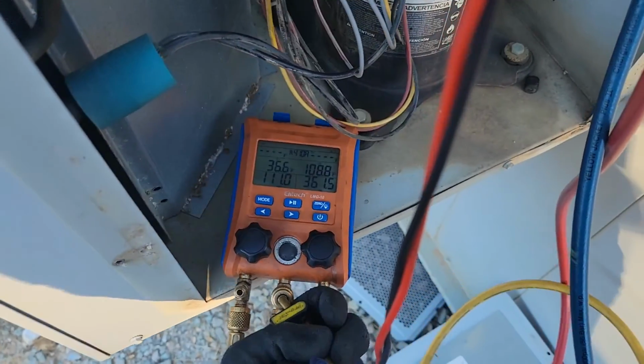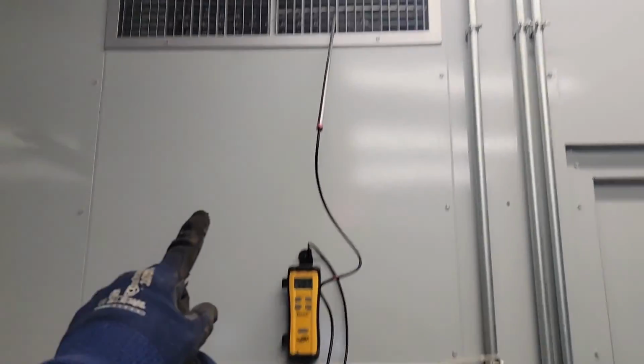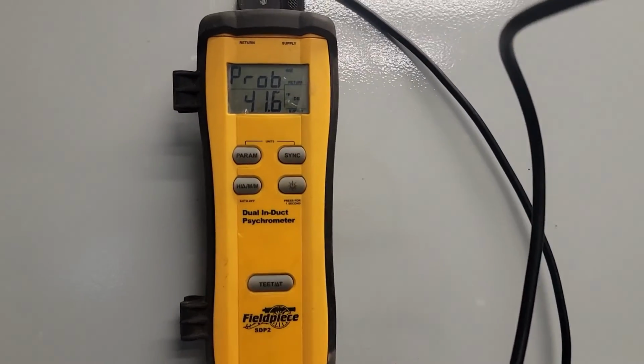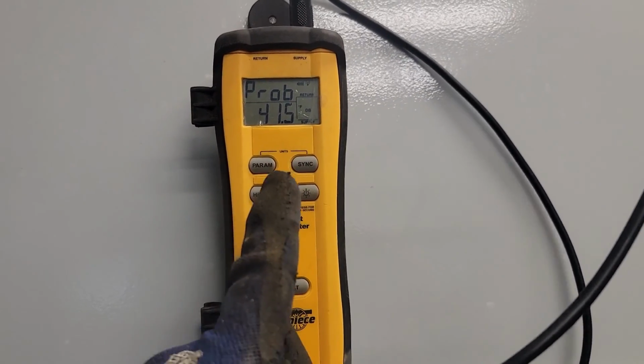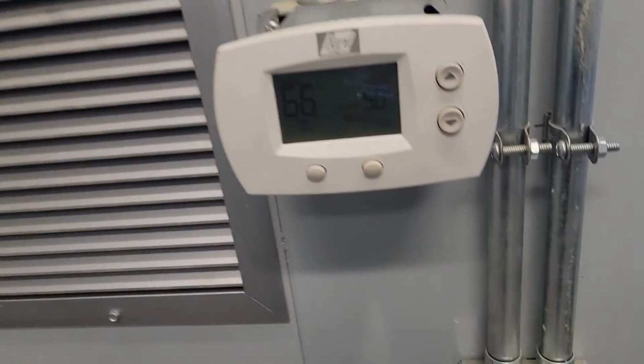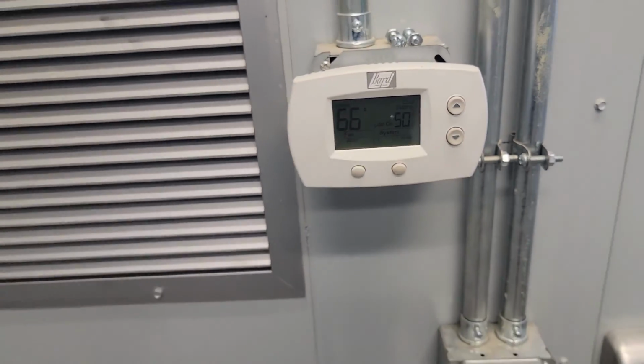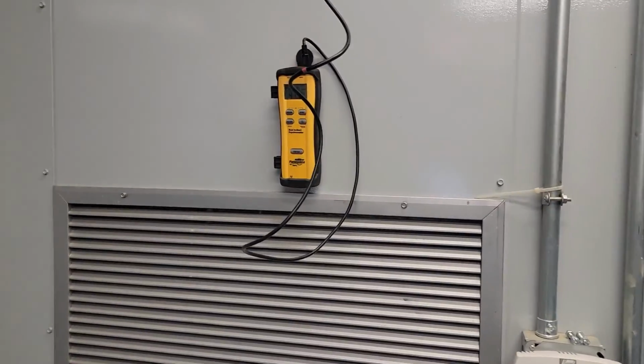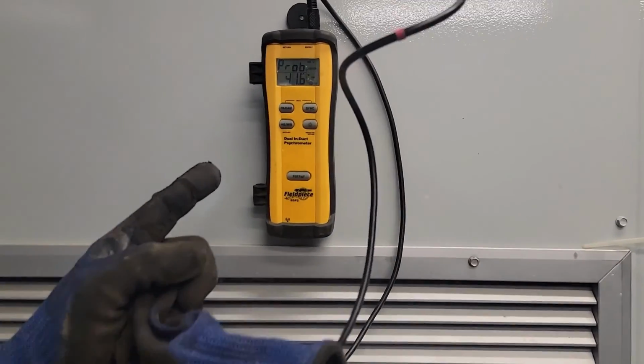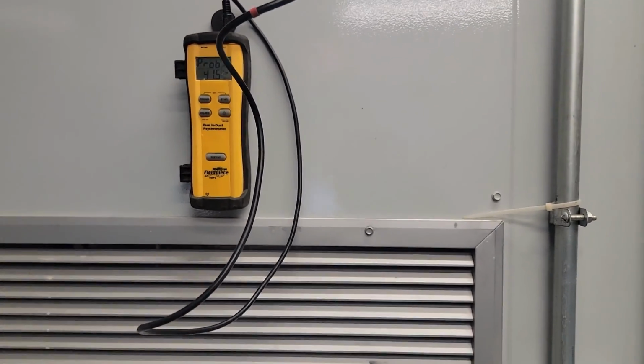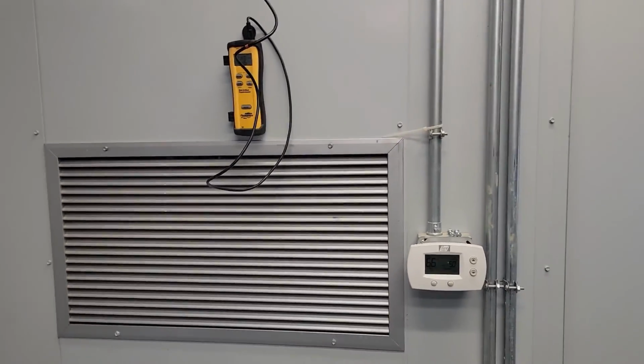That looks pretty good. This is the return, this is the supply, and we've got our dual in-duct psychrometer measuring supply air temp. It's 41 degrees. It's 66 in here, so that's a great temperature split. 46 would be 20 degrees, so we got like a 25-degree temperature split.